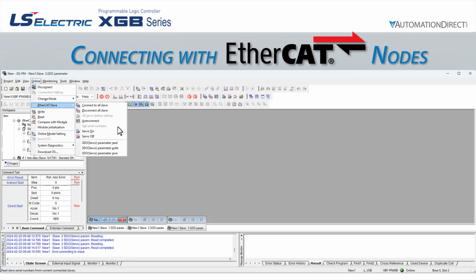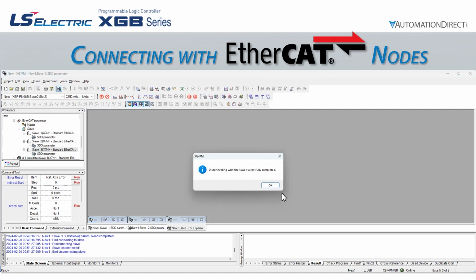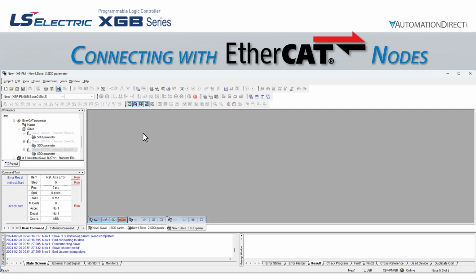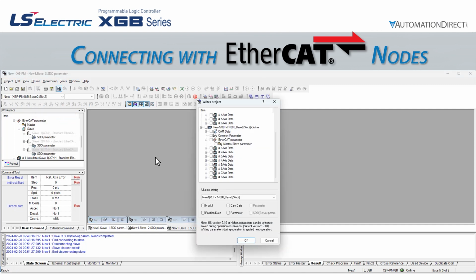To disconnect the EtherCAT network, we will select Disconnect All Slave. This will give us confirmation when the disconnection is successful. We can then click the icon of a laptop with an arrow pointing to a PLC, or we can go to Online, Write. This will pull up the Write Project window, where we can select what information we want to write. We aren't doing anything with the XEM CPU's onboard step and direction axes, so we will leave that section unchecked to save write time. Let's just check the box for the PN08B and then click OK.